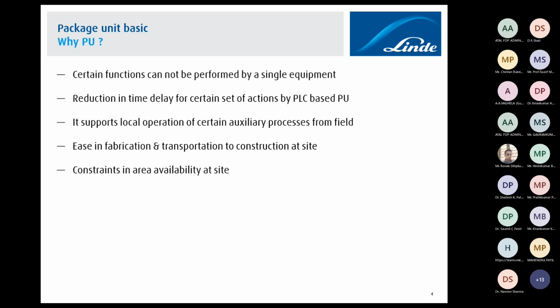It addresses constrained area availability at site, because in a typical construction site you don't have that many places. Think about it: if all that equipment is not stuffed on a skid, and is placed locally side by side, then it also requires a lot of space. So basically, wherever there is a space constraint, it helps to narrow down the space requirement. It assists in continuous operation of the main process plant, because ultimately the package unit is there to support the main process. We should not forget why we are installing it, because our overall objective is to operate the plant, whether it is a hydrogen plant, ethylene cracker, LNG, or any kind of gas or chemical plant.